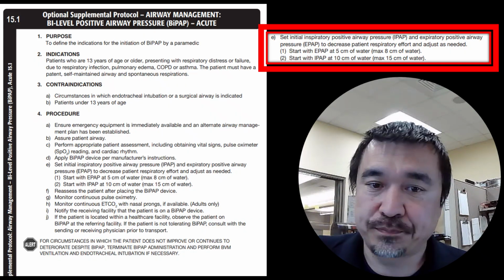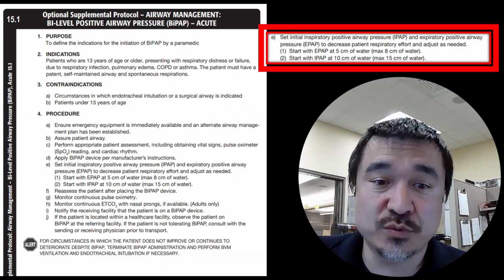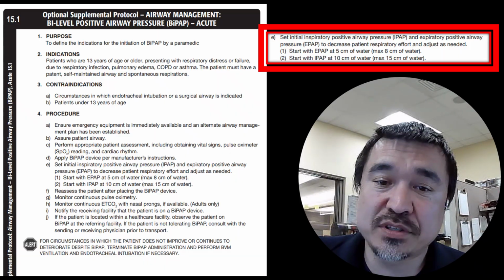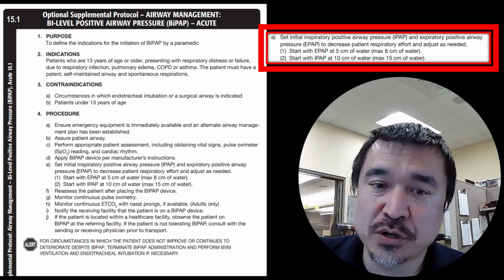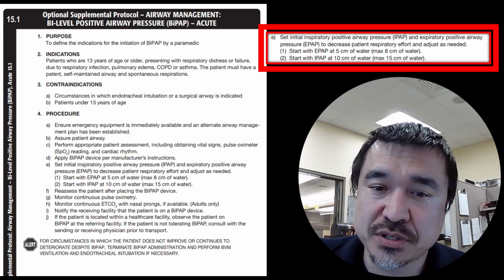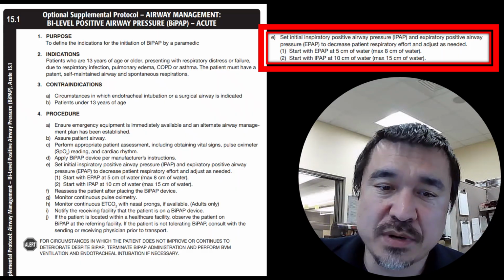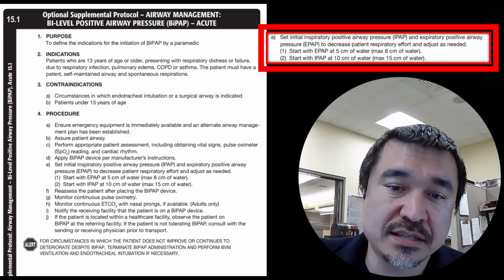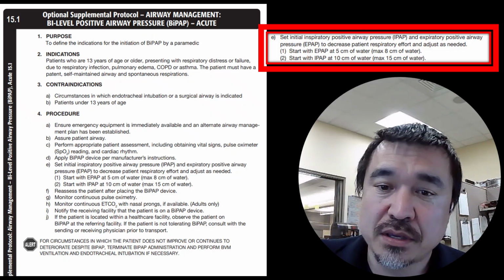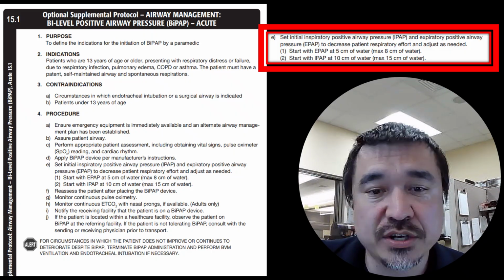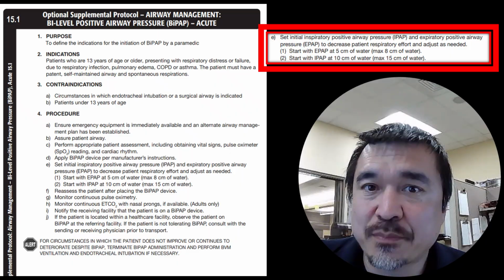So now what? What should our settings be? Where should we start? With bi-level devices, a lot of them use different terms and parameters to set the pressures. Some set the pressure by pressure support, and others set it by desired tidal volume. With the disposable one we have pictured here, we'll be setting the IPAP and the EPAP.